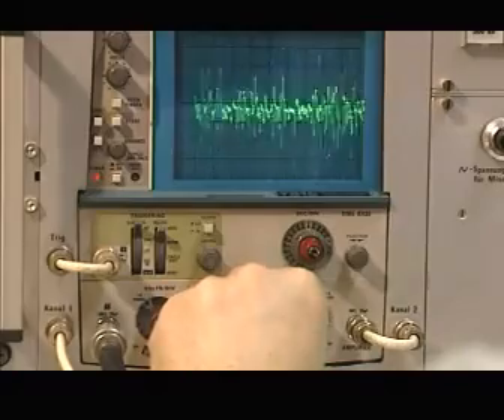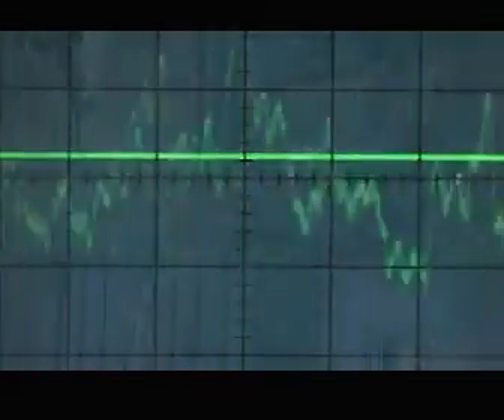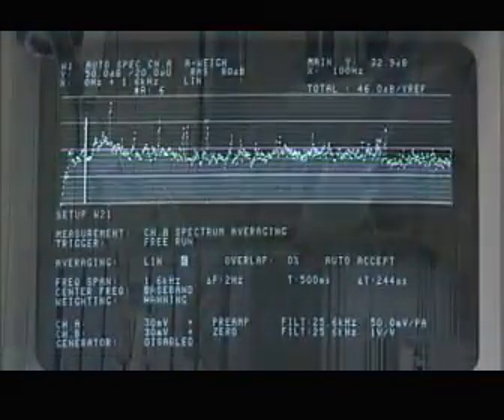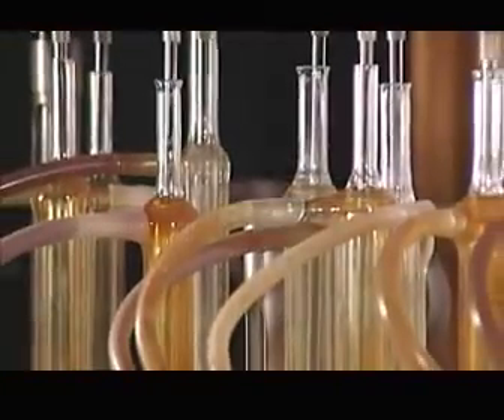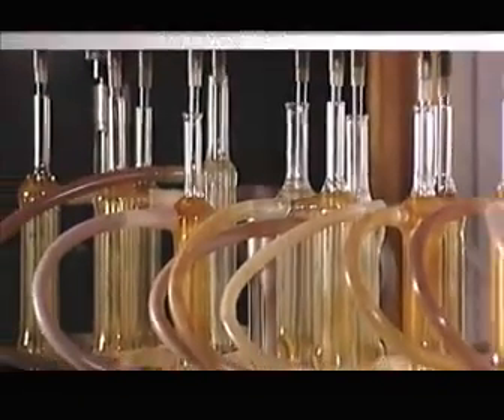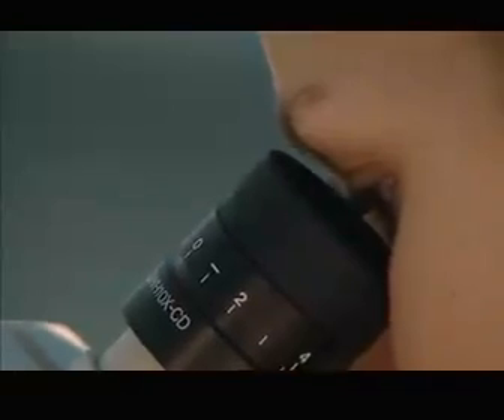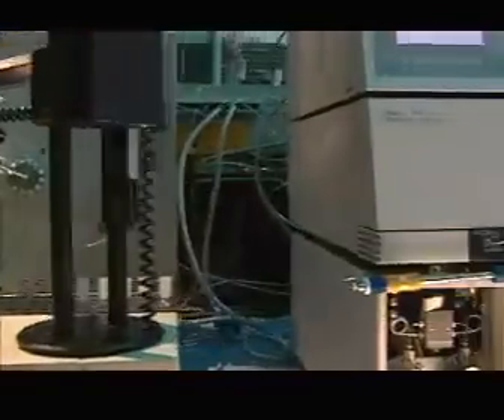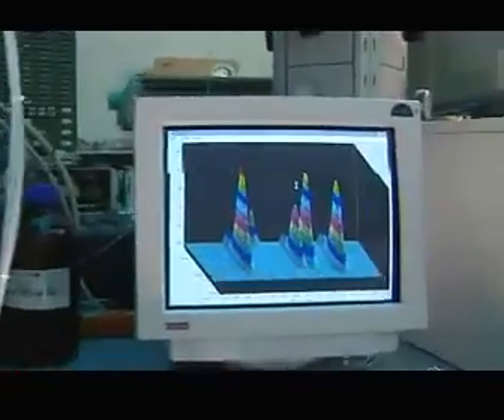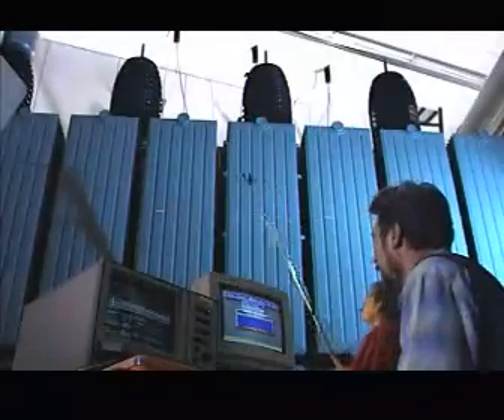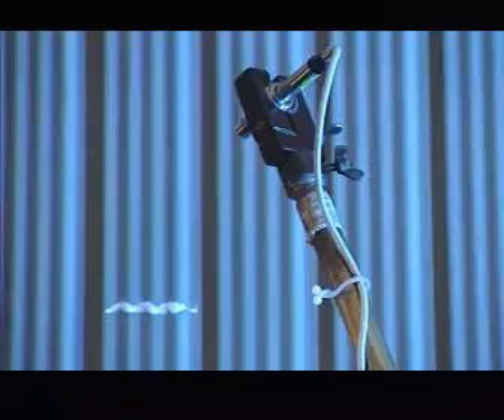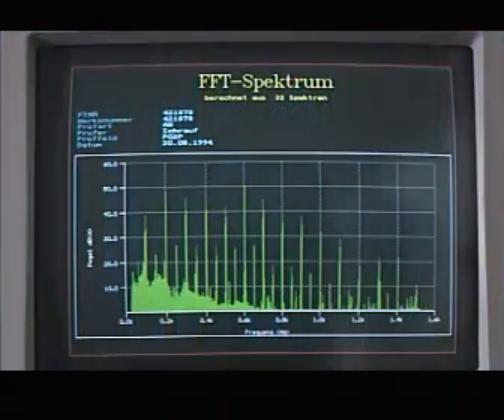Process computers control the measurement of noise level, electrical discharge and temperature rise. The test procedure is accompanied by a chemical analysis of the transformer oil. We can carry out all the relevant measurements in our modern materials testing lab. For example, furan analysis using HPLC. Low noise levels with high reliability and cost effectiveness. That's where Siemens power transformers score.